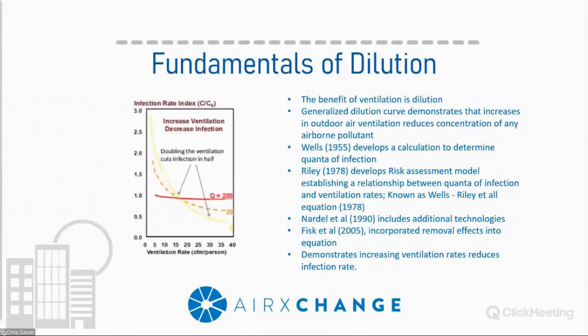So the science behind reduced infection rates as it relates to ventilation is most often attributed to what's known as the Wells-Riley equation. Back in 1955, Wells developed a way to calculate what's known as a quanta of infection. A quanta of infection is a unitless hypothetical infection dose rate. It wasn't until 1978 that Riley came along and took the quanta and developed a risk assessment model that established an infection rate reduction with increasing rates of ventilation and quanta. And looking at that relationship, it can be demonstrated that the process follows a similar curve to that of the general dilution curve.